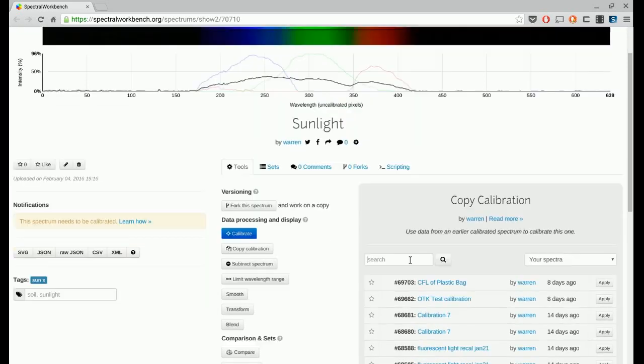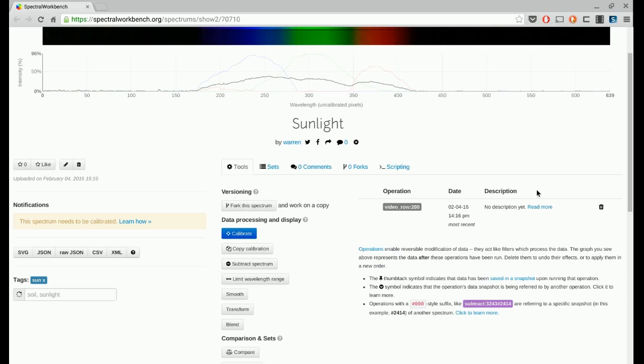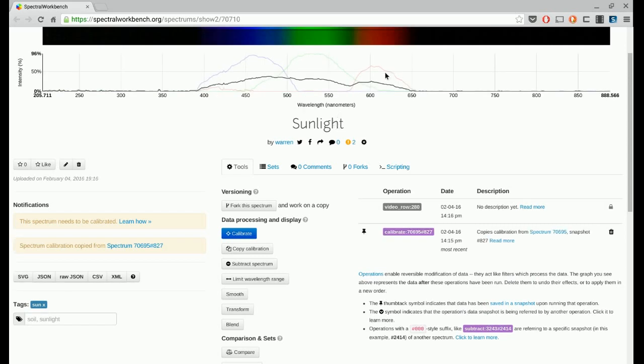Calibration itself is going to be covered in a different video, but we'll show you what you'll be doing most of the time, which is using an existing calibration. Looks good. And notice it says uncalibrated pixels, which is right. I'm going to copy calibration, and this shows recent calibrations. It's not showing that most recent one, which I made about an hour ago. Here it is. I searched for it, and I'm going to apply.